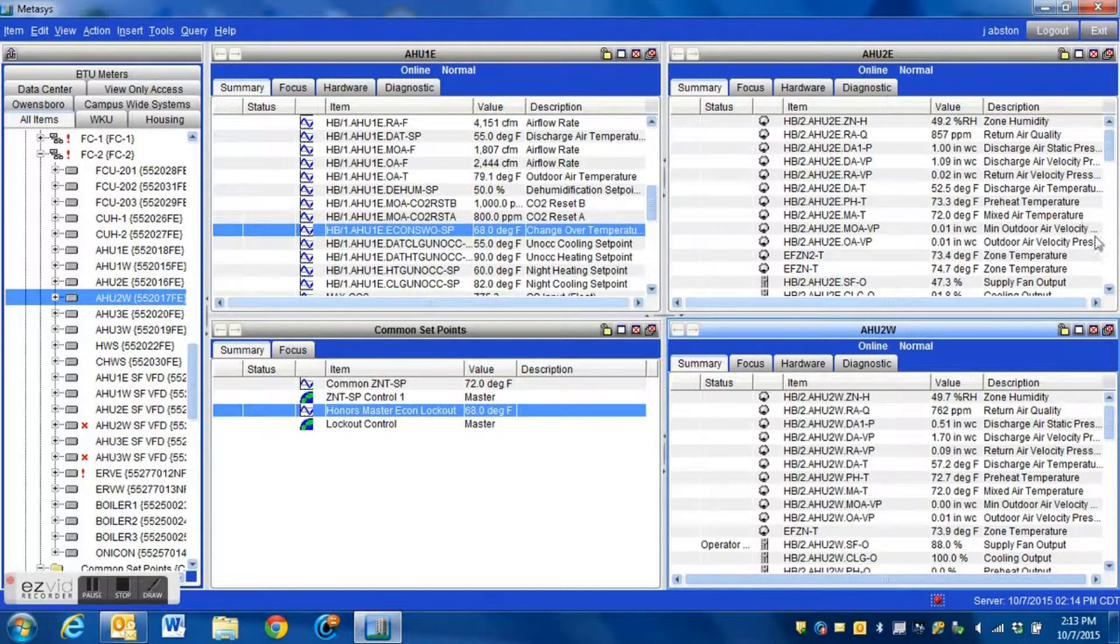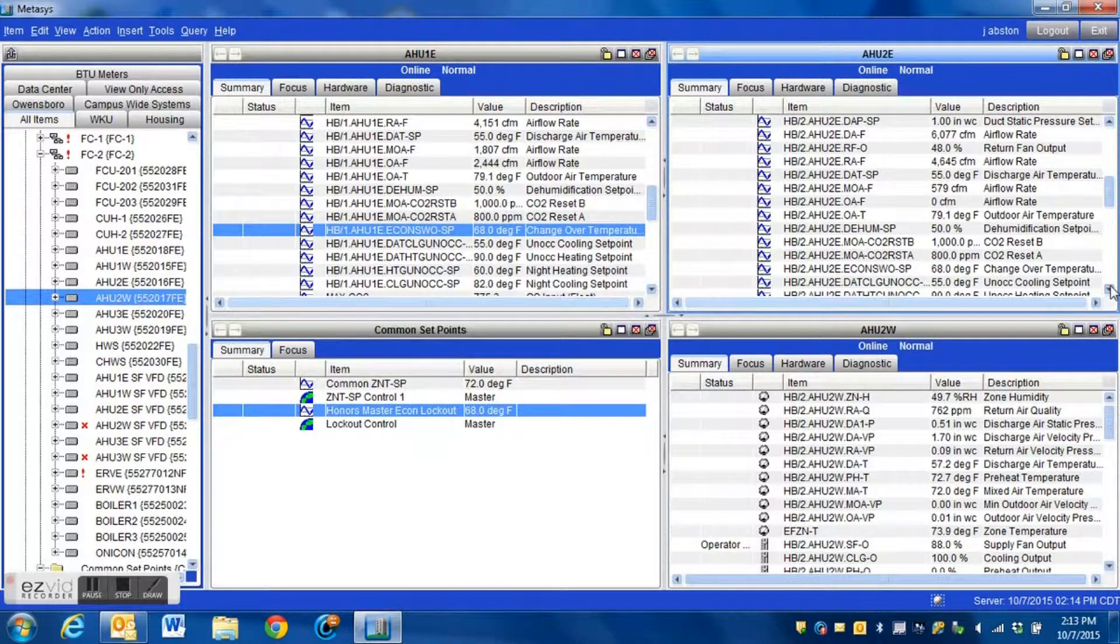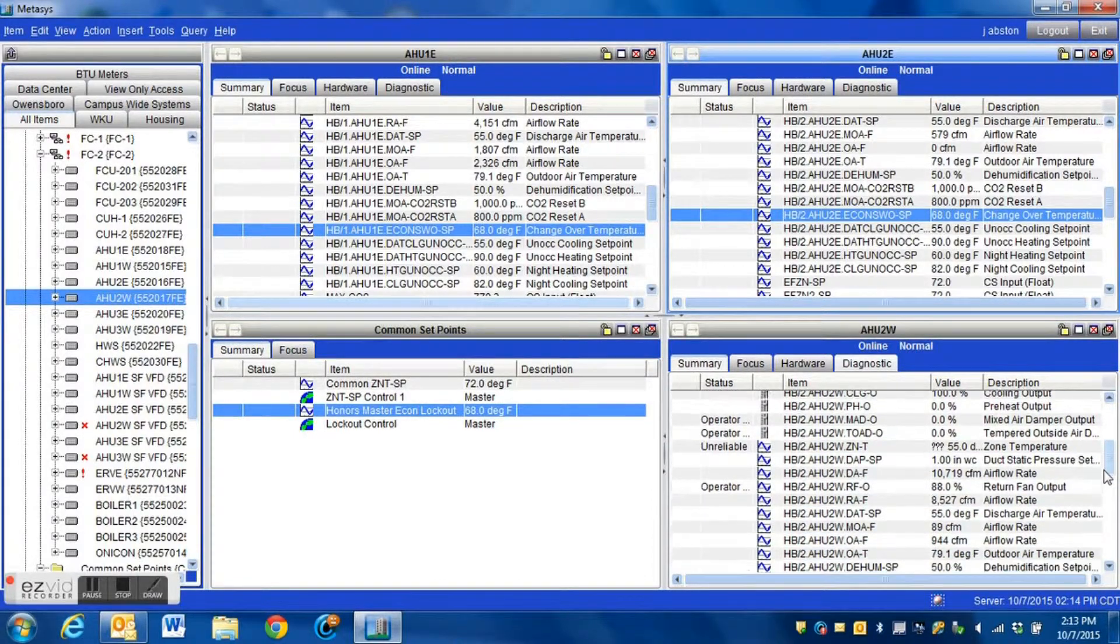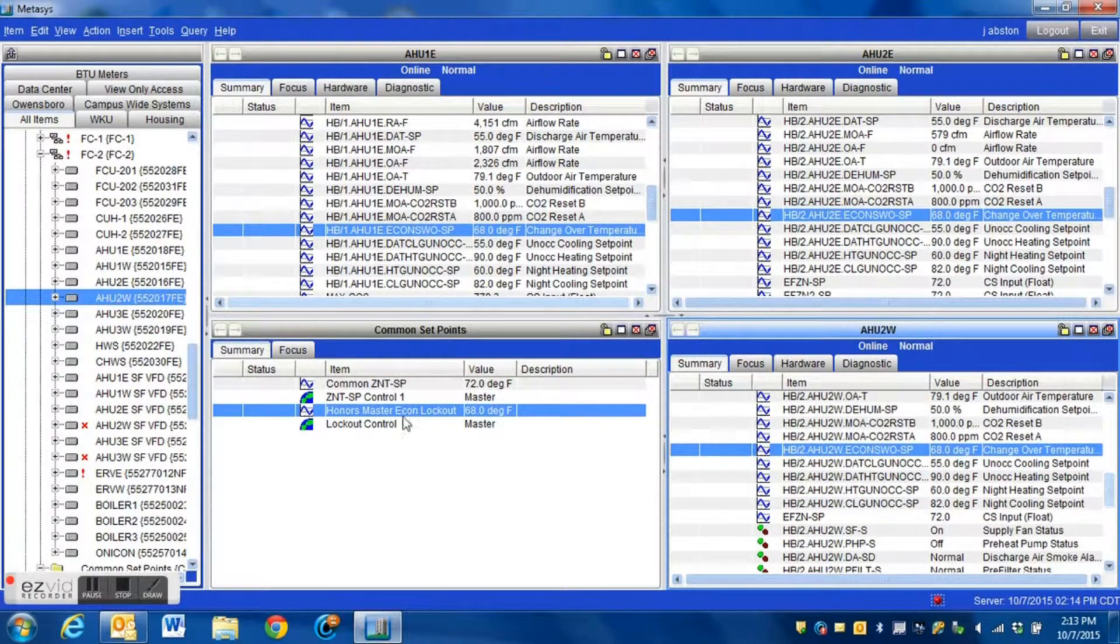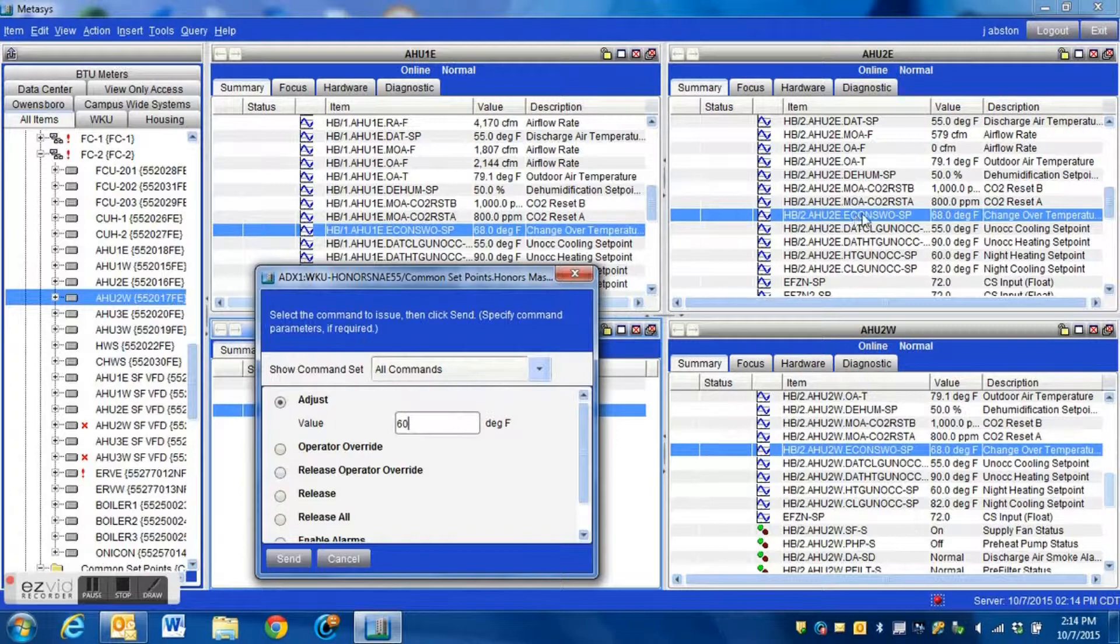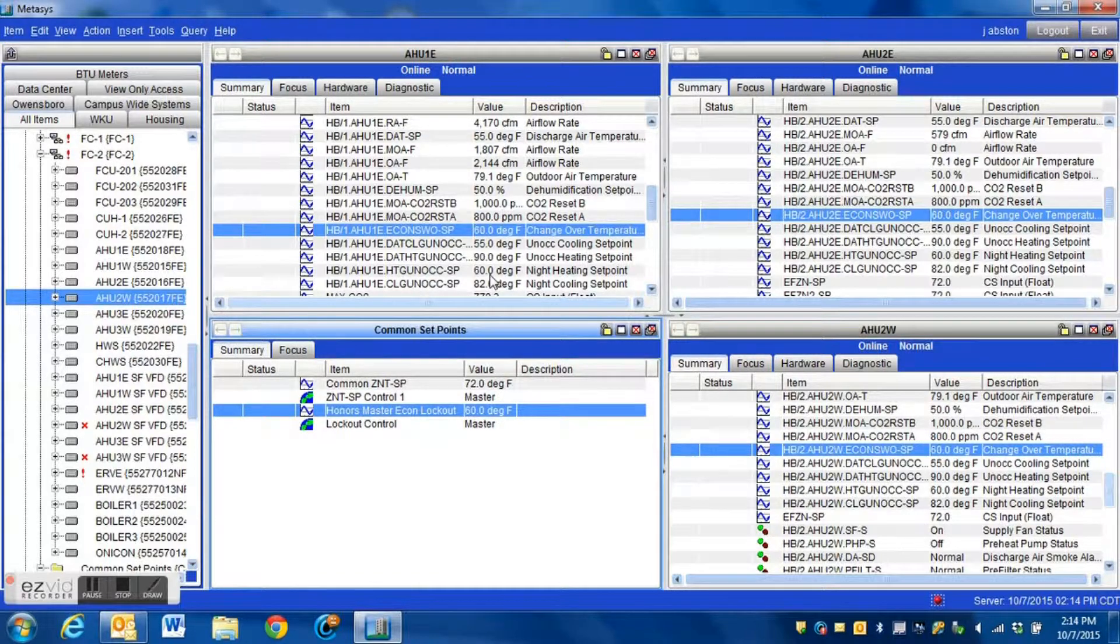Okay now then we have our air handlers, let's just find the points that we need. Okay here it is for this air handler, now then let's find it on our other one. There it is. Now watch each of those points how they react when I change just this one value. I'm simply going to adjust it and when I press the send button you can see that it will change that value in each of those units instead of having to change multiple values. You can simply let the computer do the work for you.